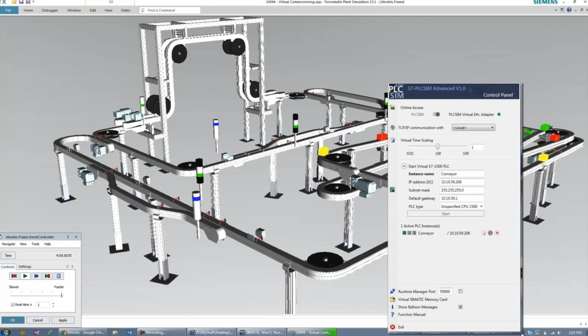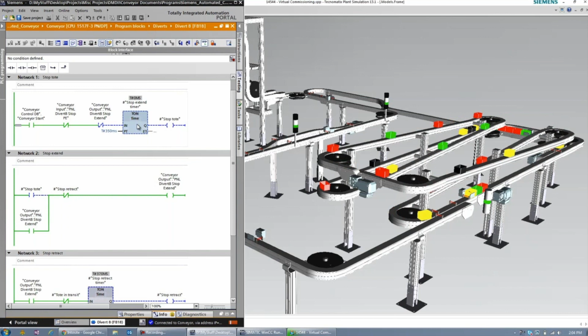Now that I have that, here's my ladder logic that I'm testing on that PLC. You can see this gate here that I've highlighted. If I look at my ladder logic, I can see this changing up here. Watch next time that changes, and as soon as it does, it releases a box from the line. They're stopped and paused until that tells me to go, and that's when they release. So I can actually see the ladder logic driving the simulation.